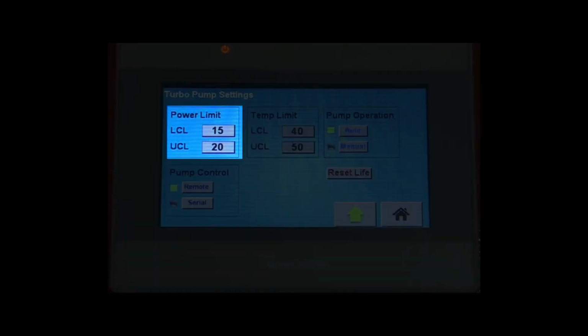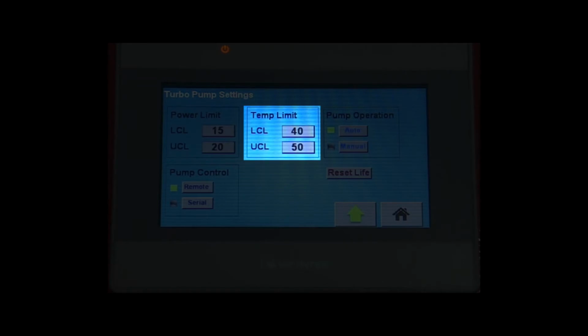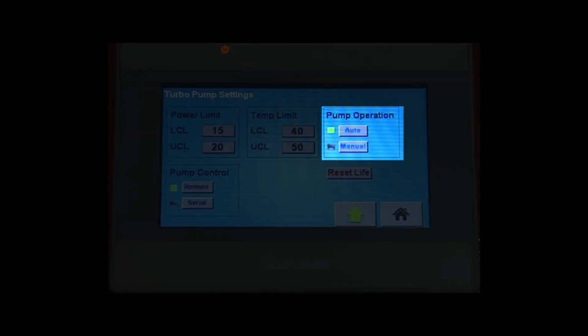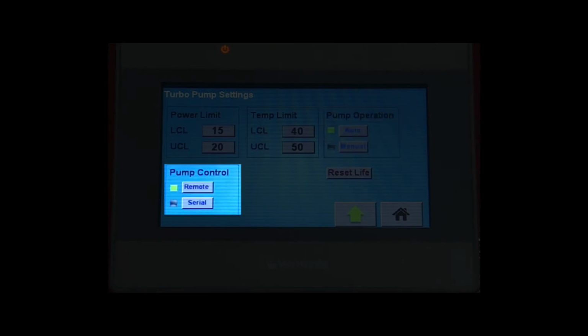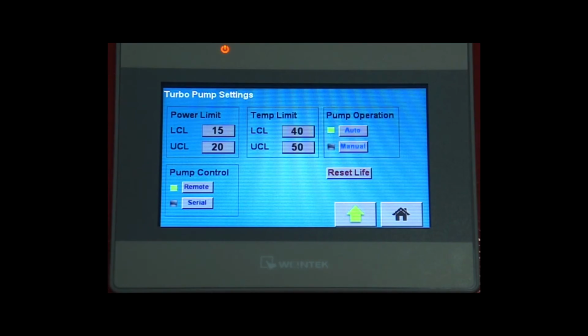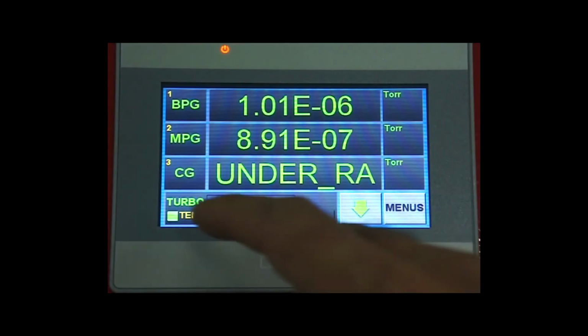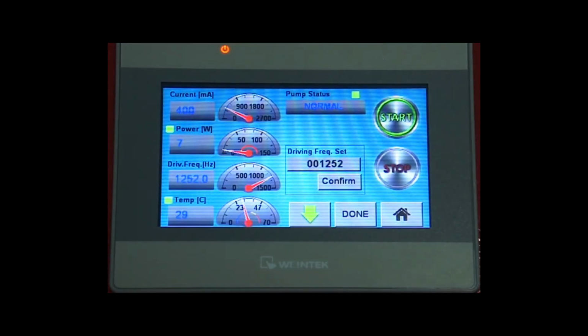You can set up the power limit or temperature limit or pump operation. You can set it on auto mode, which is protection mode, or manual mode. And you can also set up the pump control to remote or serial. Press turbo on the screen for more info and functions of the turbo pump.